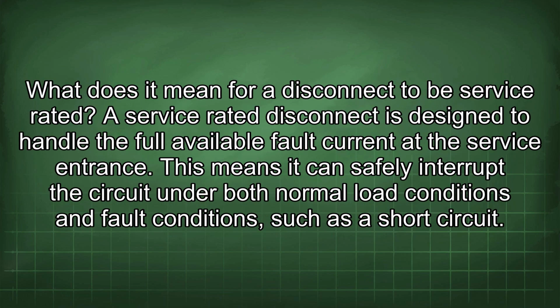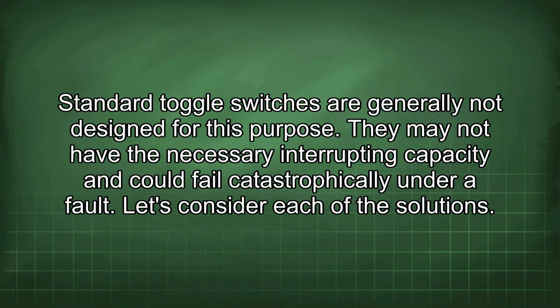What does it mean for a disconnect to be service rated? A service rated disconnect is designed to handle the full available fault current at the service entrance. This means it can safely interrupt the circuit under both normal load conditions and fault conditions, such as a short circuit. Standard toggle switches are generally not designed for this purpose. They may not have the necessary interrupting capacity and could fail catastrophically under a fault. Let's consider each of the solutions.